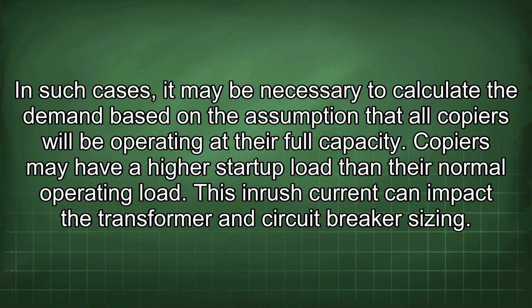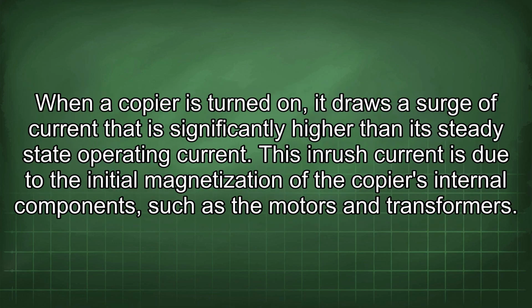Copiers may have a higher startup load than their normal operating load. This inrush current can impact the transformer and circuit breaker sizing. When a copier is turned on, it draws a surge of current that is significantly higher than its steady-state operating current.